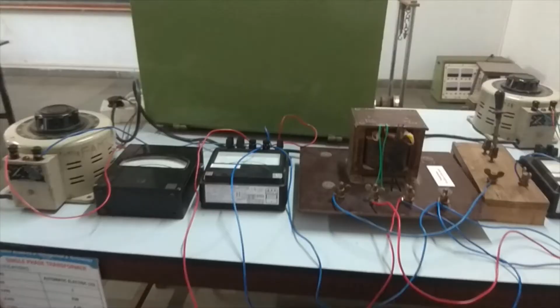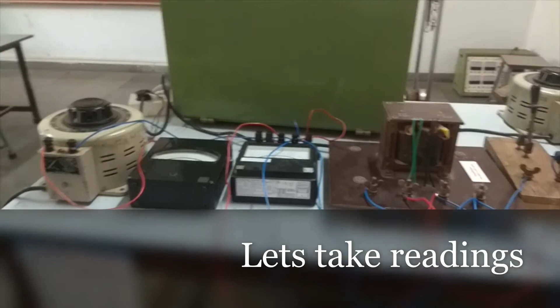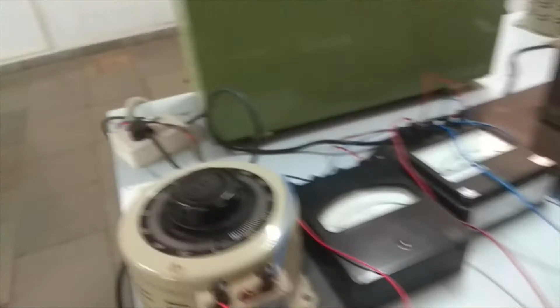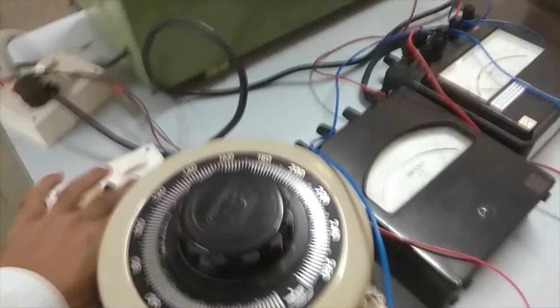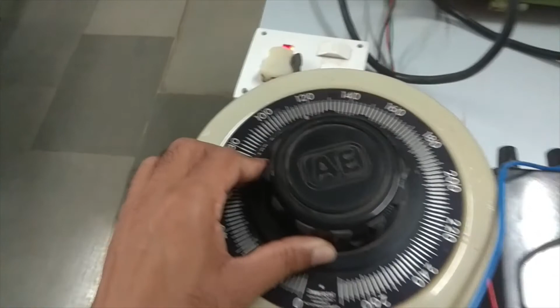We are using a 5 ampere wattmeter here. So these are the connections. Hopefully it is clear to you that we have made connections according to the circuit diagram, and then we are going to take the reading. We have made connections for the Sumpner test, and now we are going to switch on the supply. First we will switch on the supply of the primary side, and now we have switched it on. Then we will inject the voltage with the variac, and it will be set to 115 volt. So that is the primary voltage, 115 volt.